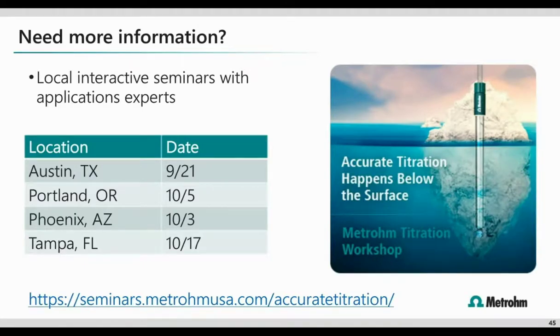Excellent, thank you. Now, our next question has to do with calibrating, and how often do you recommend calibration? We recommend calibrating every day that you're using your pH meter and your electrode. If you're not using it for the day, you won't have to bother calibrating it, but if you are using your electrode that day, we do recommend calibrating it, just for a pH measurement. If you're titrating, then you won't really need to calibrate your pH electrode. However, if you are having problems with your titration, we do recommend performing a calibration in regards to troubleshooting your electrode.